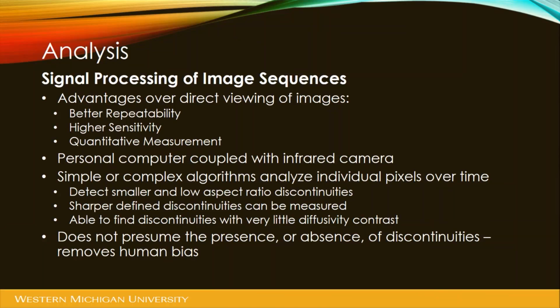The place where I went to learn how to do this was hosted at a facility that takes thermal cameras and integrates them into production lines where they seal plastic packaging. As soon as the plastic packaging is sealed, a thermal image is taken of it, and a computer looks at that image and says, yes, it was properly sealed, or no, there's a cold spot here, so it wouldn't have melted the plastic together, or it got too hot and could have melted through rather than bonding two pieces together. That was all done by computers.